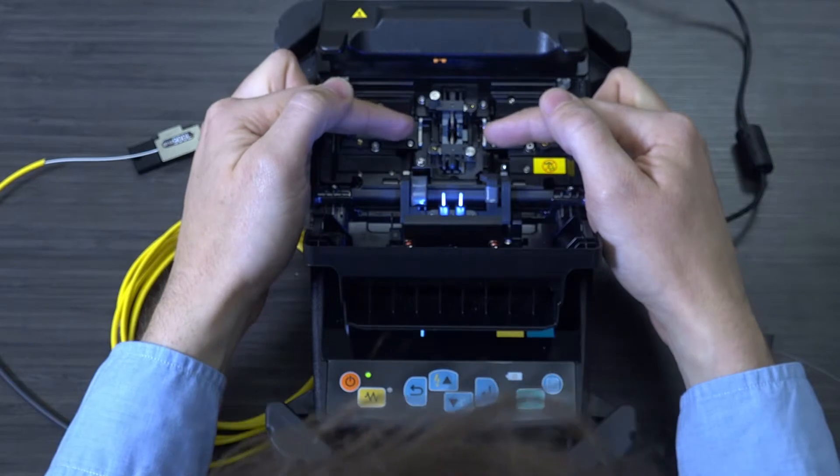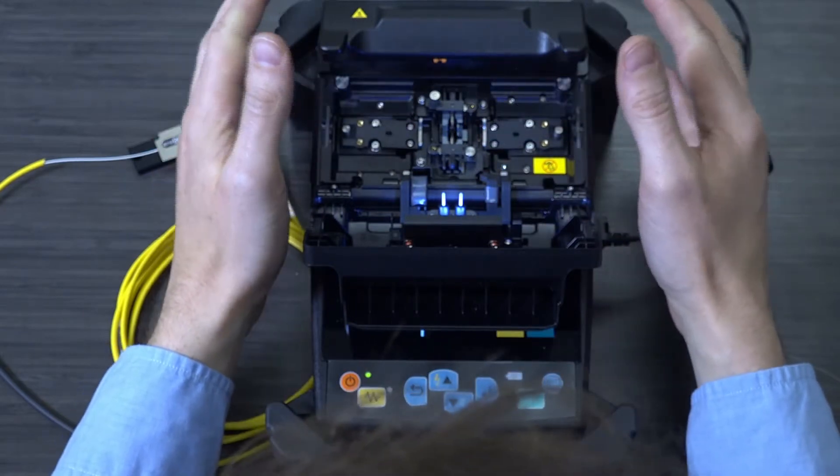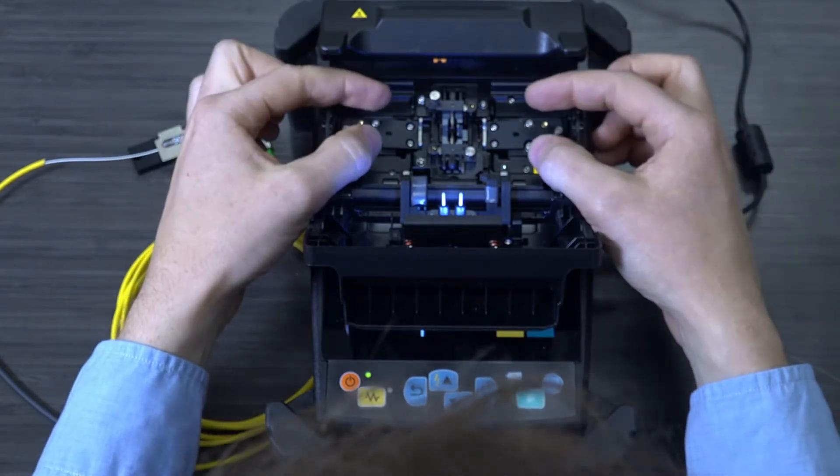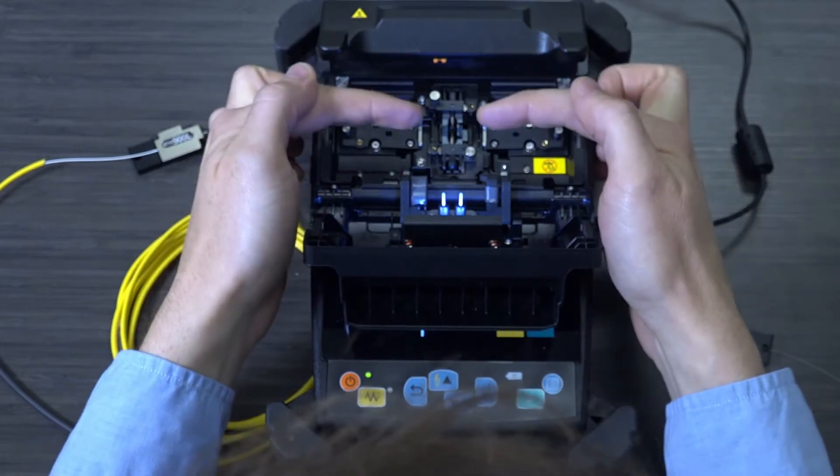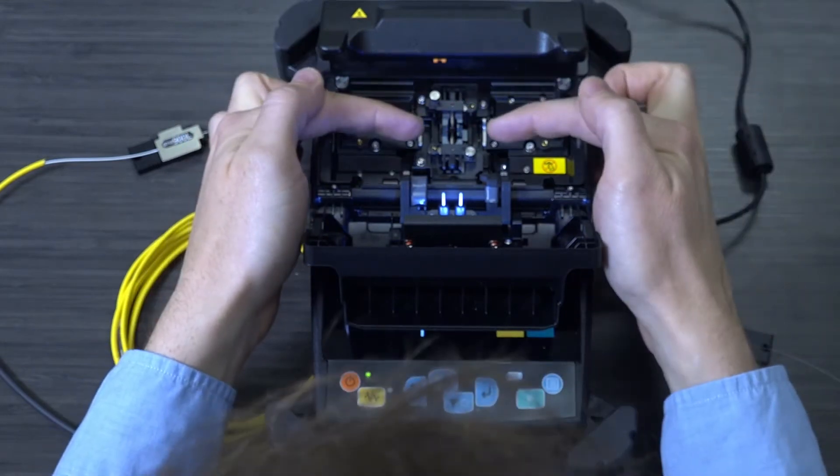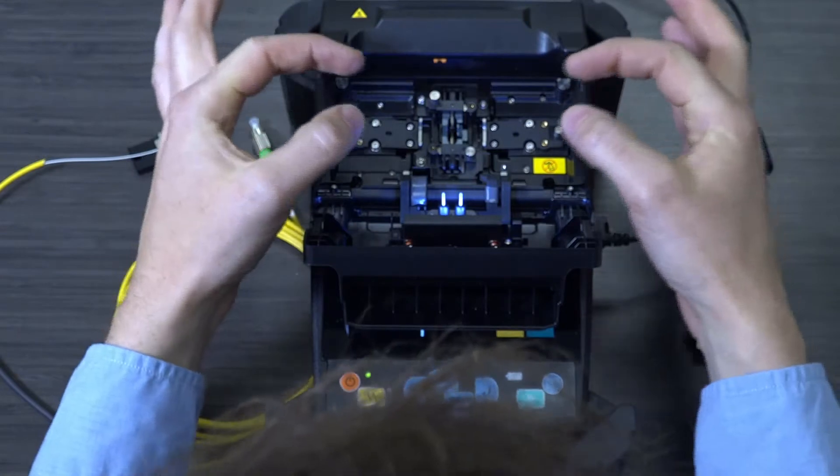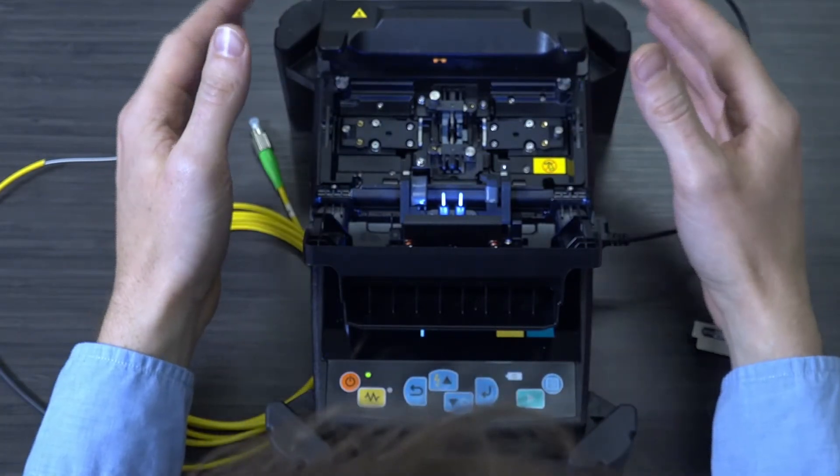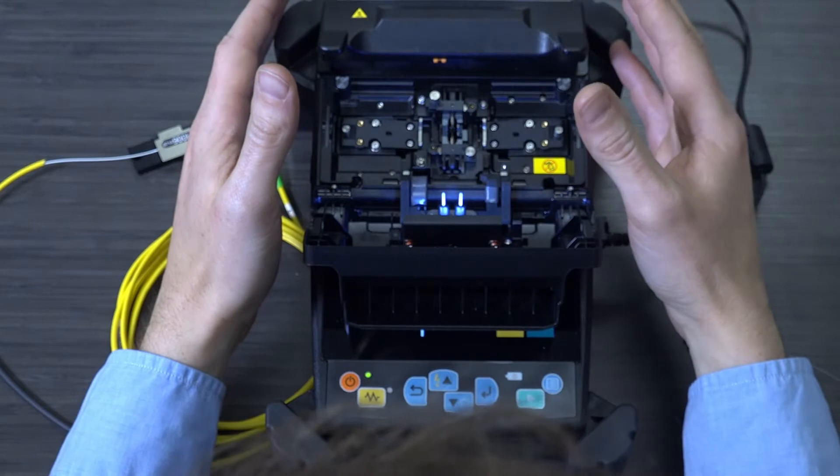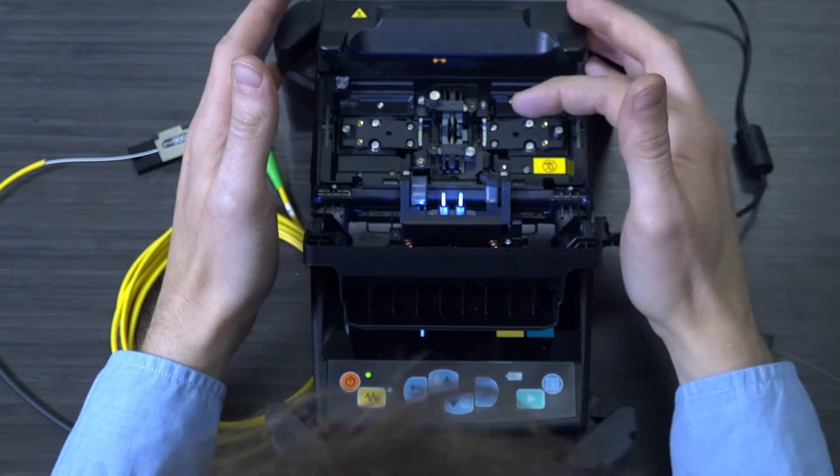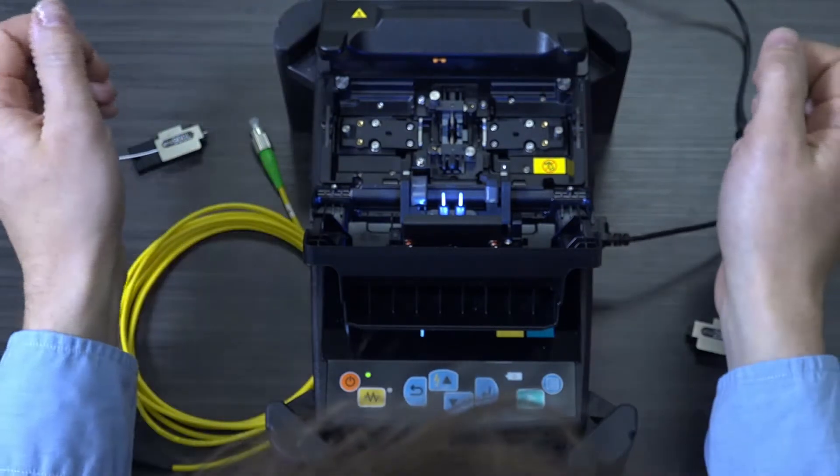So what this device will do is we will place everything in here. We will make sure the fibers are not spanning or crossing those two electrodes. They need to stay on their own sides when they're first placed. We will close this lid. The splicer will bring them together, automatically align them, and it will use these two electrodes to actually fuse the two fibers together.